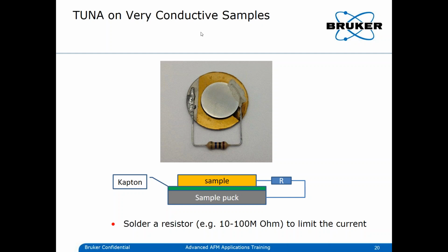And in the case you have very conductive samples like a gold layer or even HOPG, it is better to make this contact via a resistor in between, in the range of 10 to 100 megaohm, to limit the current flow. Otherwise, the TUNA is too sensitive and you show mostly only noise.